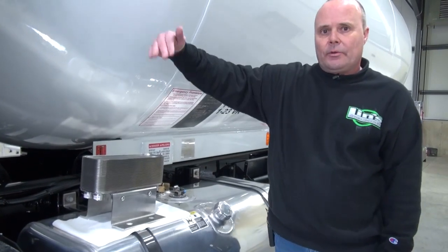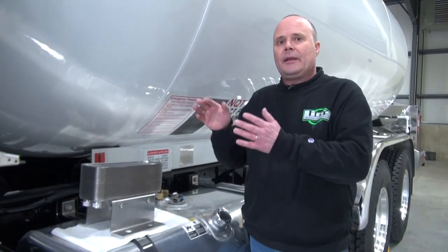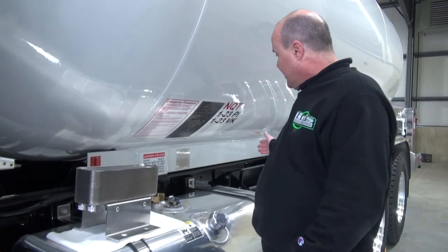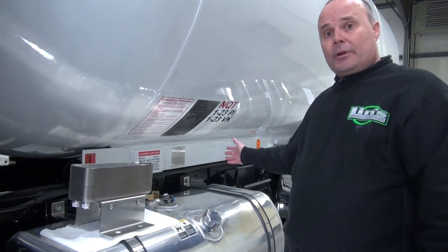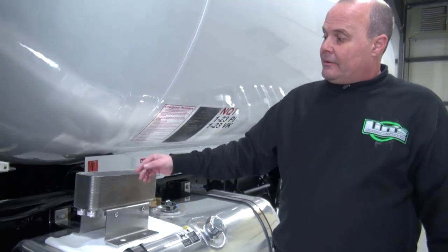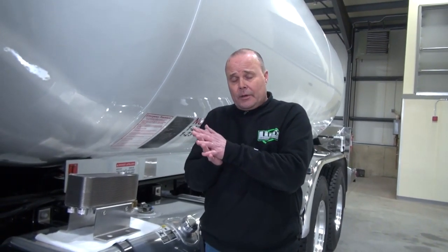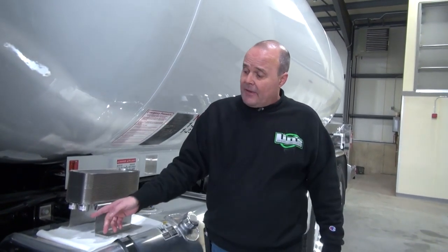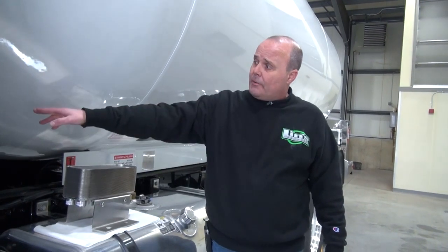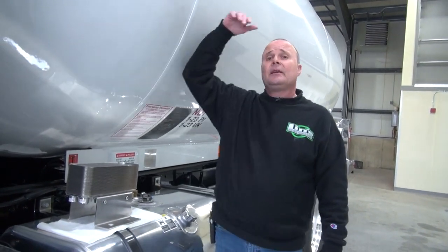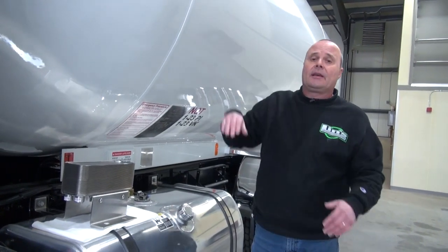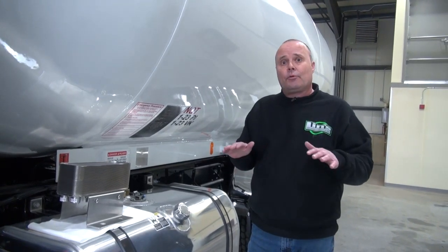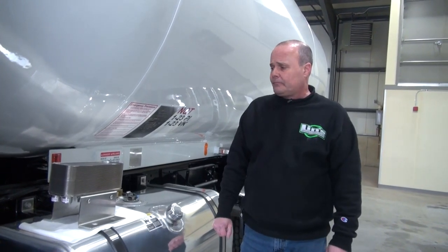So as the engine coolant flows through, it's heating the propane and vaporizing it. So the liquid will come from the discharge port at the pump, push the liquid in, it'll circulate through with the heating engine coolant as well, vaporize it, push it out through this port, back in through the head of the tank, into the vapor space on top of the tank to stabilize the liquid propane inside the tank.